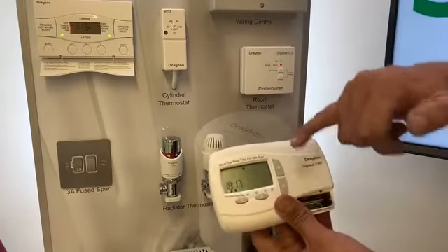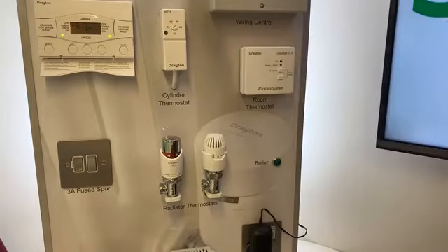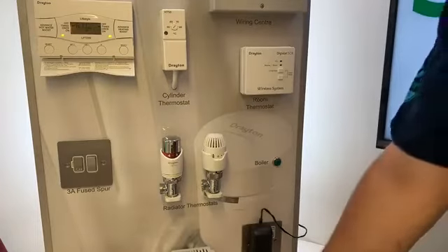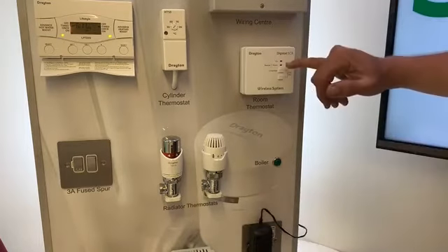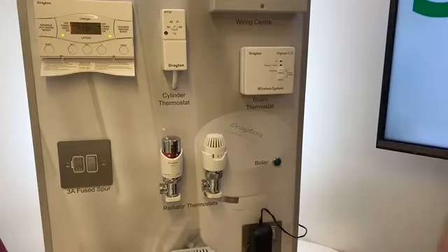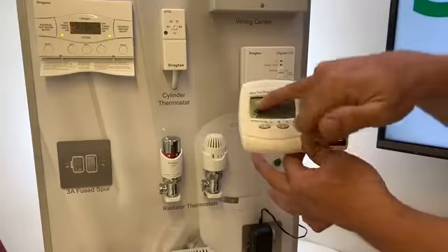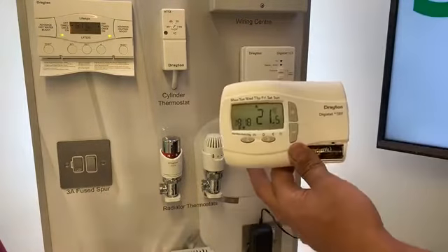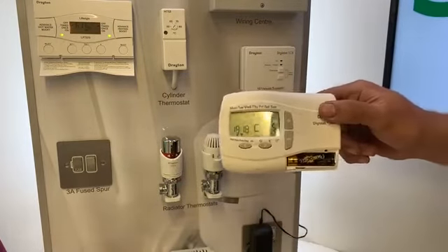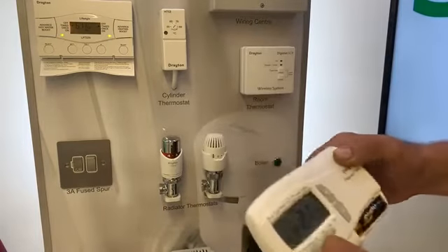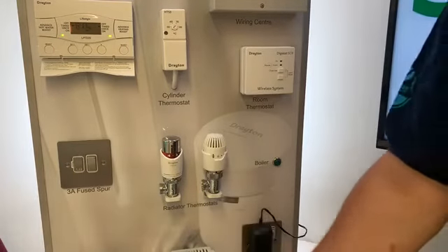Every time that this sends a signal, you'll get the receive alarm flashing. If you find that you turn up and you see the receive alarm light is pulsing, on a regular sort of pulse, it's a good indicator that the batteries need changing in this, and as such you will have a little battery indicator that comes up to show you what's going on with that if you need to change that. So that's the first demo.